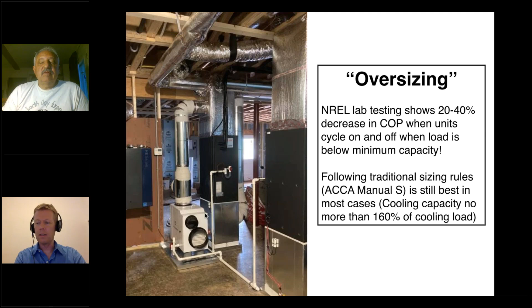So it's still best, in my opinion, to follow traditional sizing rules using ACCA Manual S in most cases, which, when you're using variable speed heat pumps, call for sizing systems so that the cooling capacity is no more than 160% of the cooling load. And then you look at your heating capacity and add supplemental heat as needed.